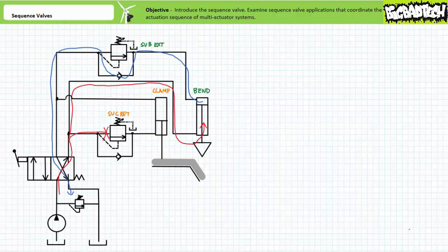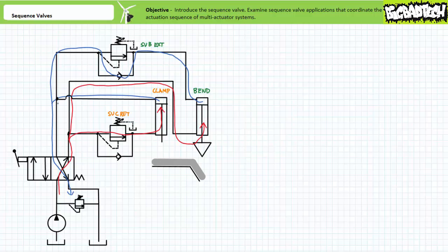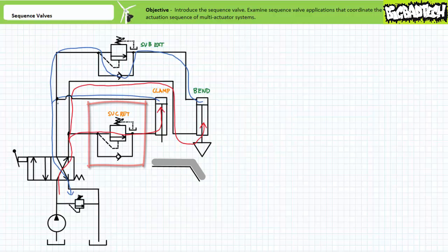When the directional control valve is shifted back to the cross connect position, the check valve bypass bypasses SVB extend and allows the bend cylinder to retract with no pressure precondition. However, the normally closed SVC retract initially prevents the retraction of the clamp cylinder. Only when the bend cylinder fully retracts does pressure rise to that of the set value of SVC retract. At this point, SVC retract maintains pressure in the primary circuit and opens, allowing the clamp cylinder to retract. Note how the pressure decision made by SVC retract coordinates the actuation sequence and SVB extend is bypassed. Long story short: retract the bend cylinder first, then retract the clamp cylinder.